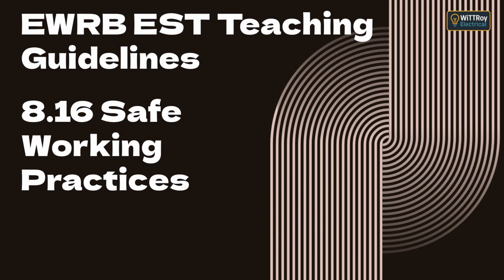Topic D, Test before touch. Now let's move to Topic D, Test before touch. This phrase is the golden rule of electrical safety. It means that before touching any conductor or terminal, you must first prove it is not live. Here's the test before touch method as spoken steps. 1. Prove your tester works on a known live source. 2. Test the circuit you're about to touch, check between active, neutral, and earth. 3. Prove your tester again on a live source to confirm it's still working. This sequence ensures you don't get a false dead reading from a faulty tester or flat battery. Remember, a test that saves a few seconds could save your life.